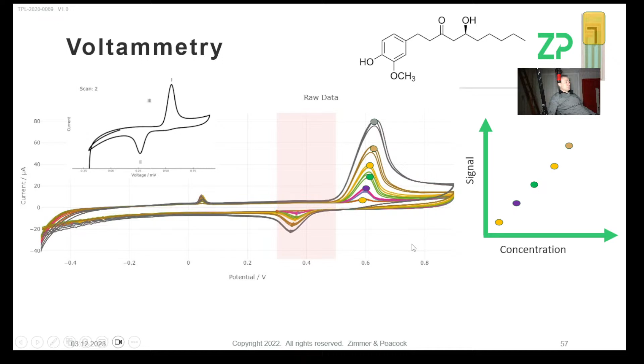So that means that when we're doing something like signal versus concentration, we've got three sensors here, 3 sensors here, 3, 3, 3. We can get very good signal versus concentration, and we don't get overlap between different concentrations because of the underlying reproducibility of the electrode, and therefore we can be calibration free in our applications.